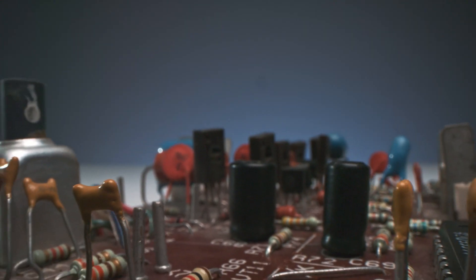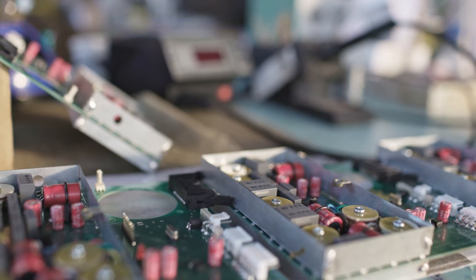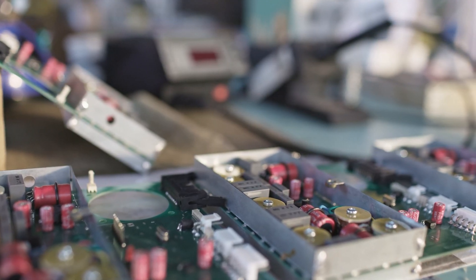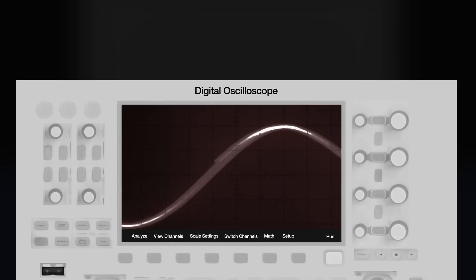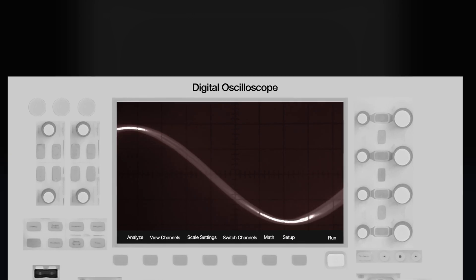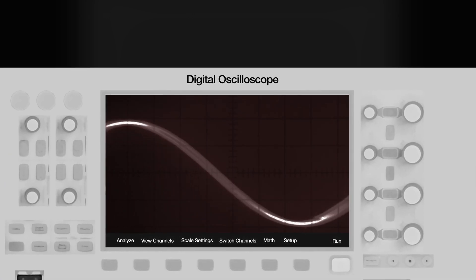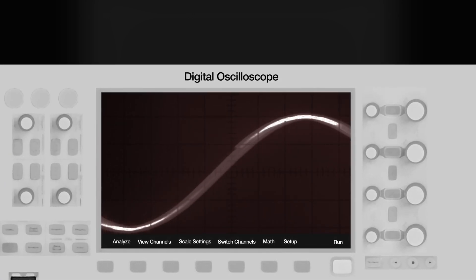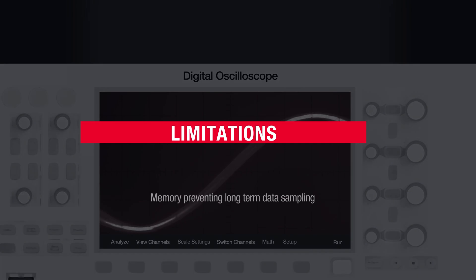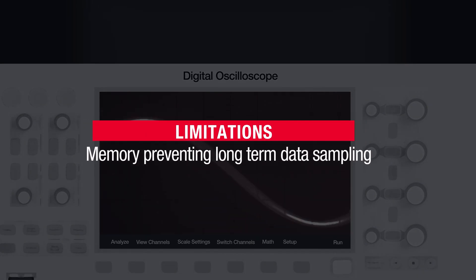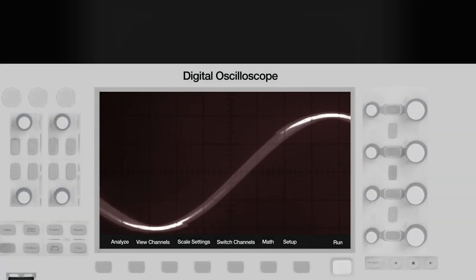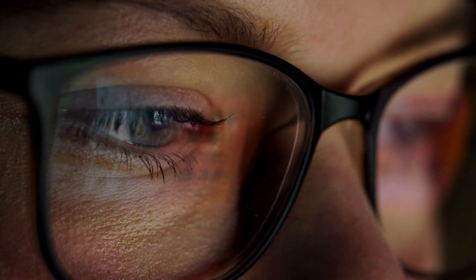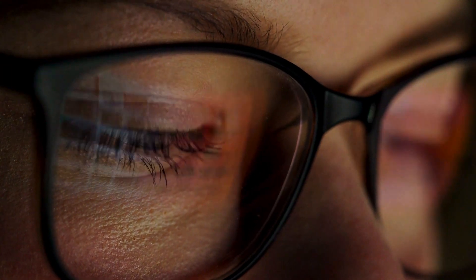There are several instruments that you can use to capture unexpected and infrequent anomalies. While an oscilloscope appears to be the best option for this, its memory limitation prevents long-term data sampling, making identifying fault locations difficult. As a result, you must keep an eye on the oscilloscope throughout the test.